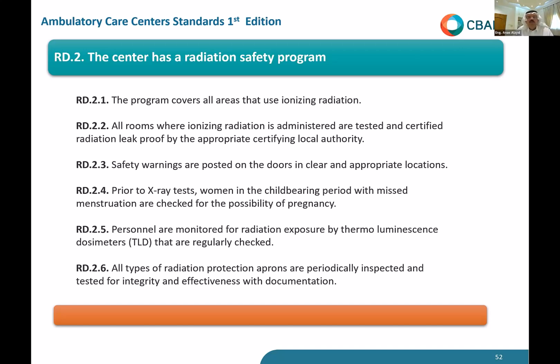Then we have all types of radiation protection aprons, which are periodically inspected and tested for integrity and effectiveness, with documentation. We need you to check the aprons, the gonad shields, and all of the protection equipment. It's very easy. If you have fluoroscopy, you put the apron under the fluoroscopy, and if there are any holes or things, you can see them. If not, you need to have a contract with an outside vendor or a clinic or somebody who can do the test for you and give you certification that the test was done.